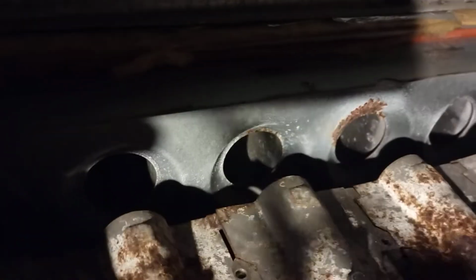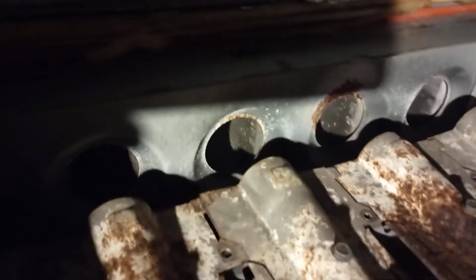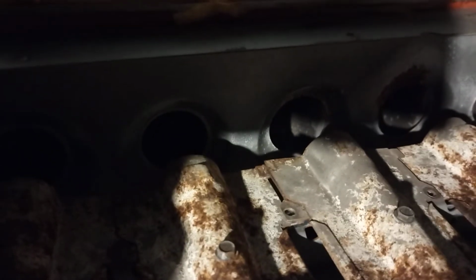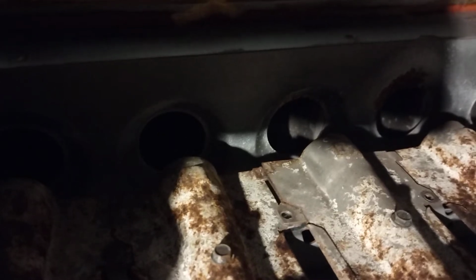And then we were able to jump start the blower motor alone to an electric plug outlet using a little gizmo like this: some alligator clips attached onto an old extension cord. When we did that, we found that indeed there was nothing wrong with the heat exchanger. If the heat exchanger is cracked or broken, the blower motor is going to be forcing all kinds of air through it and up through the exit vent, the heating vent. And if they're cracked, that flame is going to start being drawn or flickering in a certain direction.